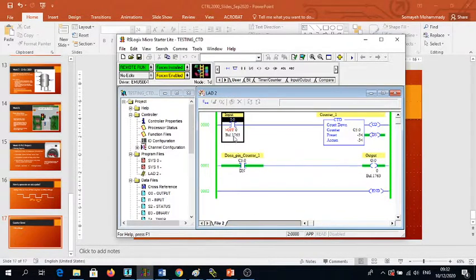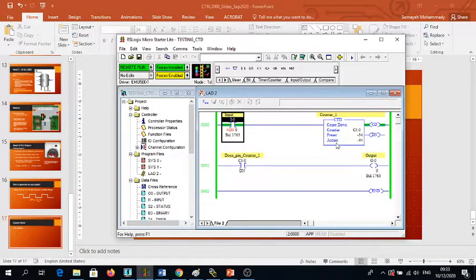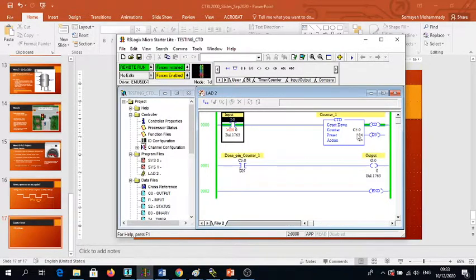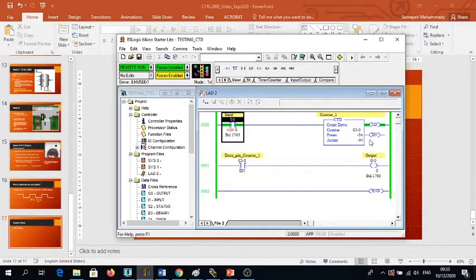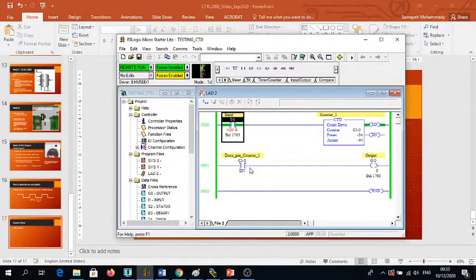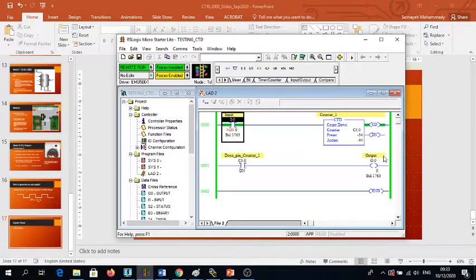Take the force off and then the next one. As you can see, my accumulated value is lower than my preset value. This is -4 and this is -3. So the done pin is not energized anymore, and also the connected contact and the output. So this would be the main difference between the Counter Down and Counter Up.